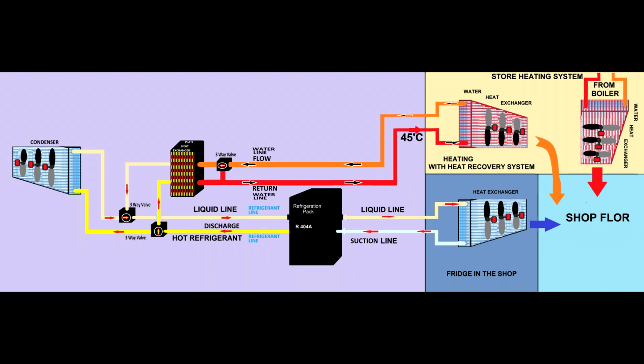Anyway, if you look into the system, you can see you have the heat recovery system, you have the refrigeration heat exchanger at the bottom, and then on the top on the left-hand side you have the heat recovery heat exchanger, and then you have the separate heat exchangers, with the heating agent temperature controlled by a boiler. So that boiler creates the heat, the refrigeration equipment tries to take the heat out, and the heat is recovered through this heat exchanger plate, which heats the water to bring the energy back into this shop.